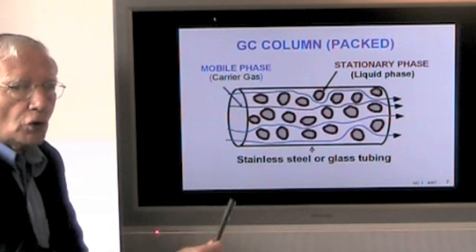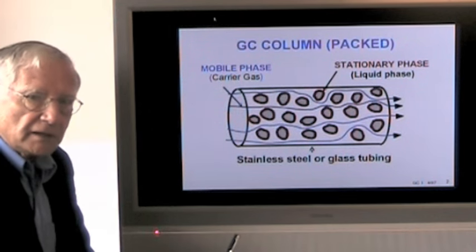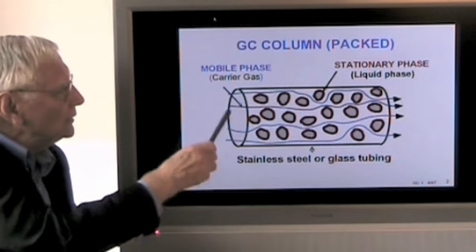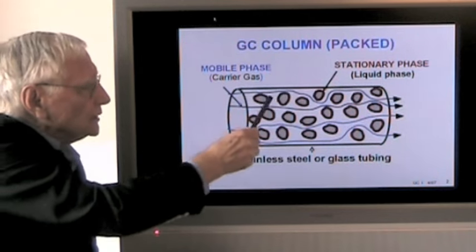The mobile phase is also called a carrier gas. Typically, it's helium, sometimes nitrogen, sometimes hydrogen. The carrier gas flows constantly through the column.